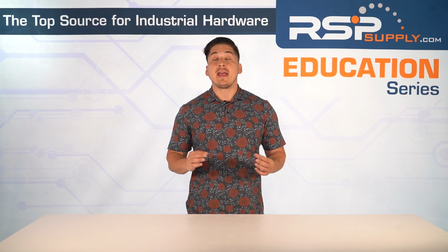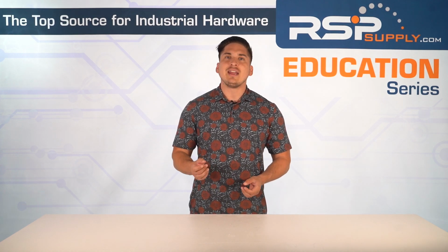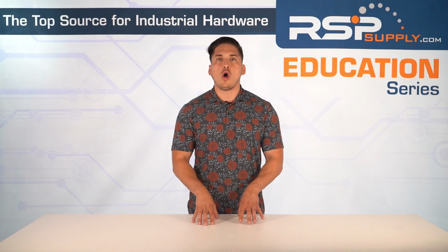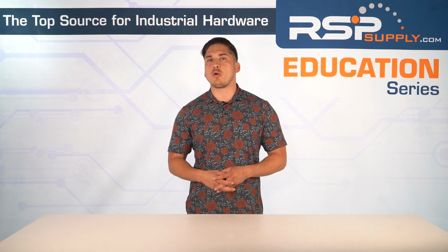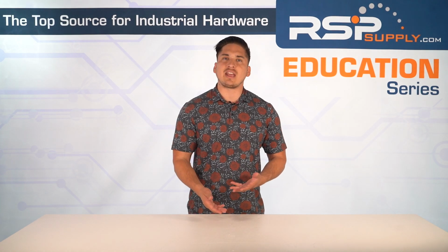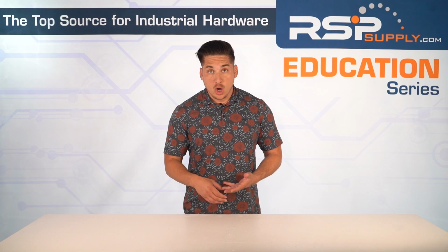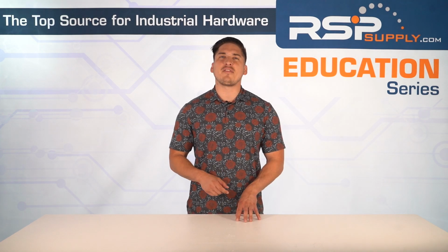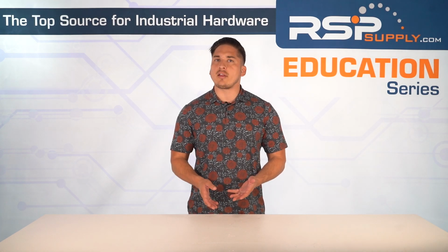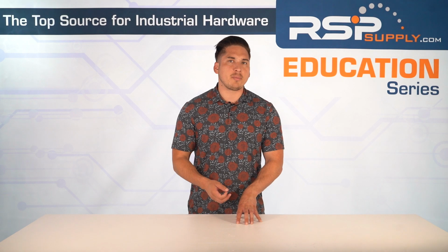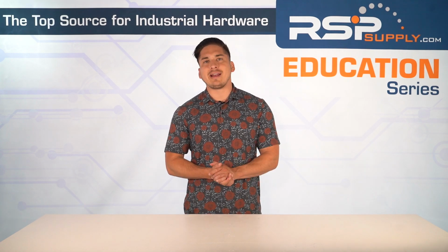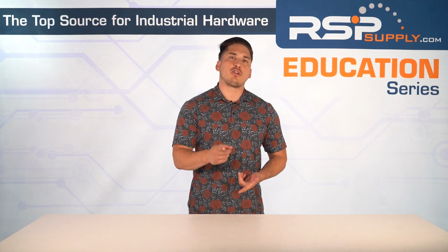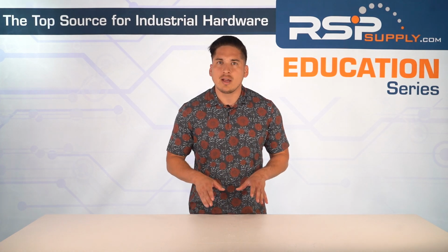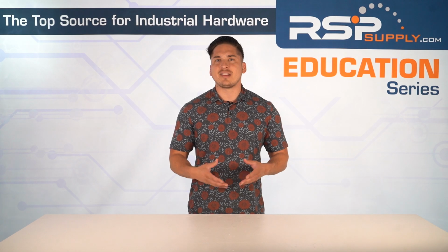So here's what to take away. Enclosed disconnects are built for safety and survival, essential for dirty, wet, or public environments. Open frame disconnects, these work great inside sealed cabinets where cost and airflow matter more than exposure. Knife blade switches are rugged but risky. Use them when arc flash isn't a concern. Rotary disconnects, these give you clean, safe operation in tight spaces. Molded case disconnects, these offer more serious current handling and safe switching. Perfect when you need something between a switch and a breaker. Bottom line is, match your disconnect to your environment and your application. It's not just about switching power, it's about safety, reliability, and system design that makes sense.